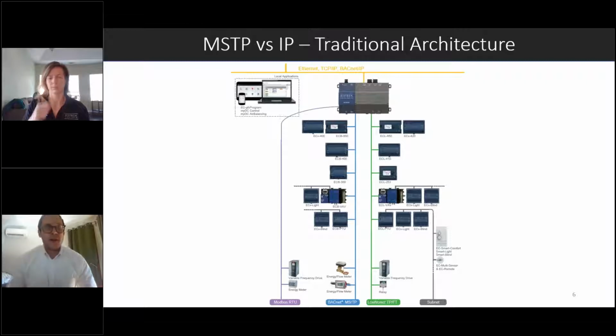We're going to show you how networking can be done a little bit differently on the IP side of things. Starting with MSTP or LON or Modbus RTU, these strategies typically use a building level controller - that's this guy up at the top - and they daisy chain all the unit level controllers back to this building level controller, which ensures everybody's working together, playing nicely, combining control strategies, scheduling, and so on.